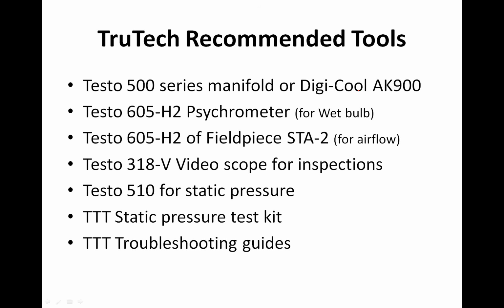A video scope is very handy for inspections of the evaporator coil. Typically, you can pull the limit out, fish the video scope up underneath the evaporator coil to see if that coil is dirty. Testo 510 for static pressure, and we do carry some static pressure test kits, and I'm going to take you here in a second and show you where the guides are.